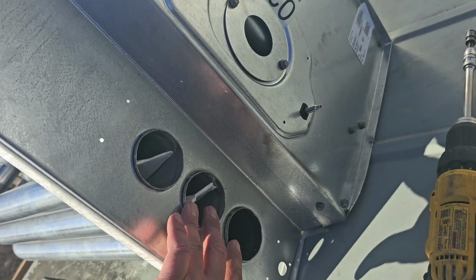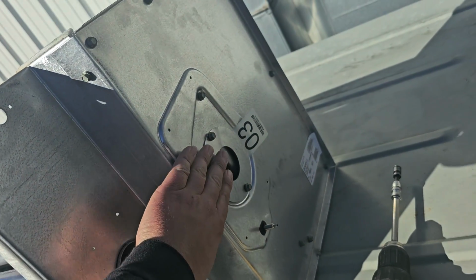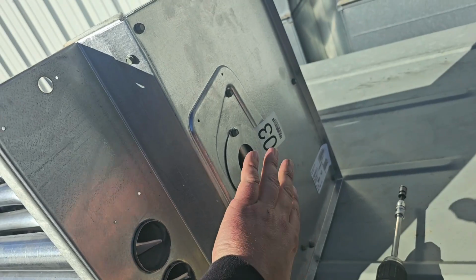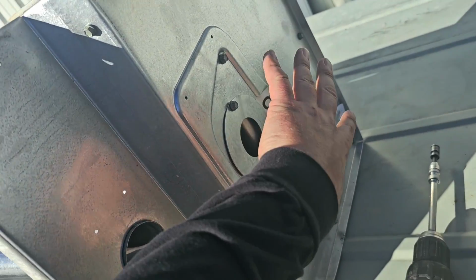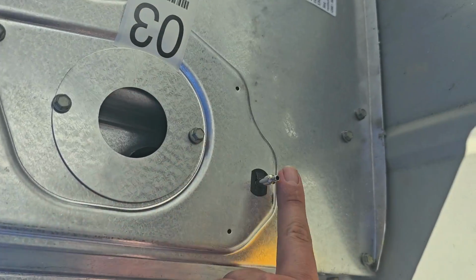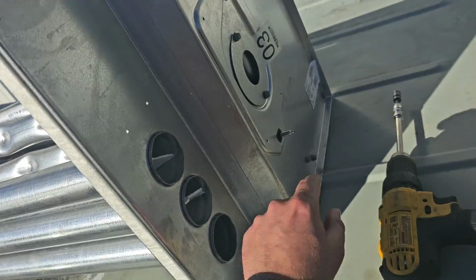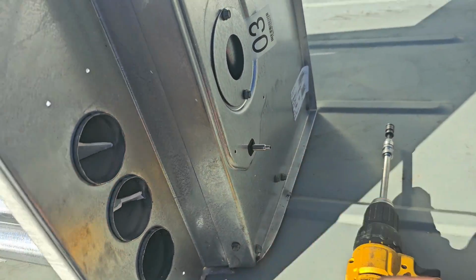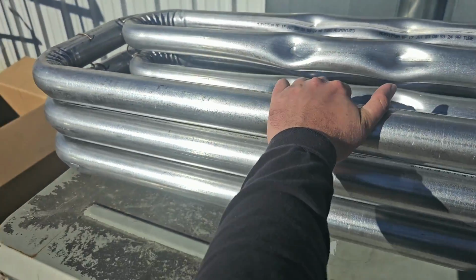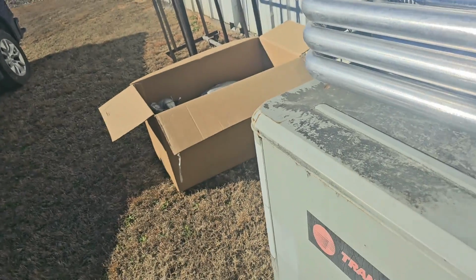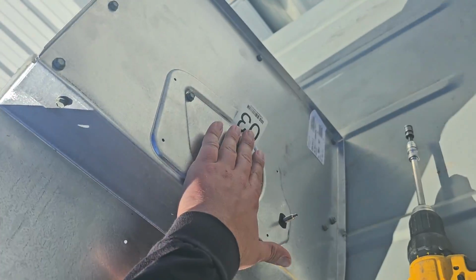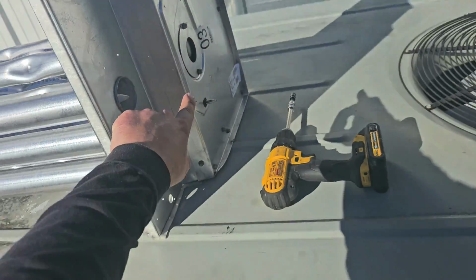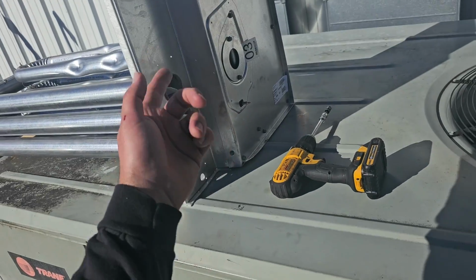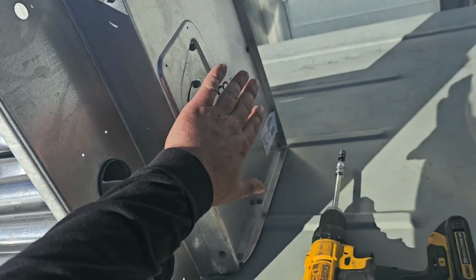You can see we've got 3 burners, and it came with the flue box cover. So this right here is the flue box. This is where the inducer motor would mount. This is where the tube would go for the pressure switch. And this is the heat exchanger. That's the box that it came in. We actually ordered a flue box cover. I've already replaced the inducer motor. I did that last year, so we shouldn't need that part of it.